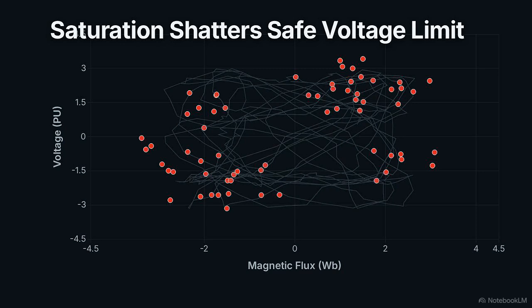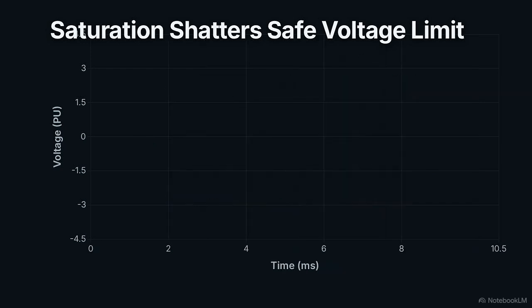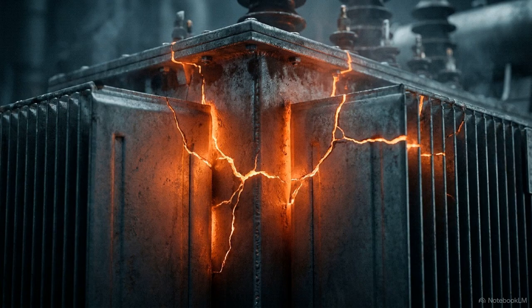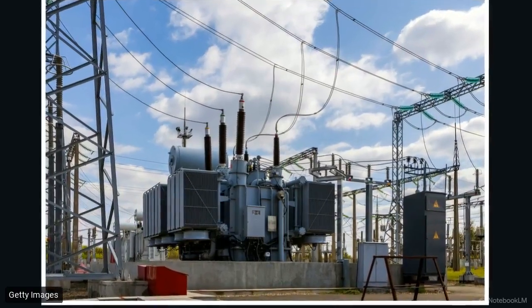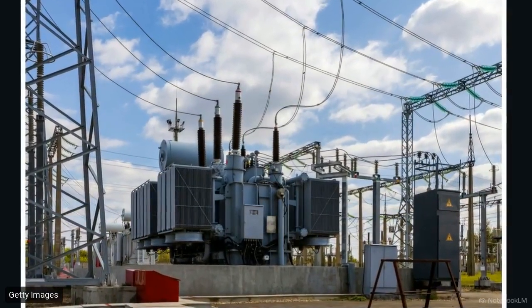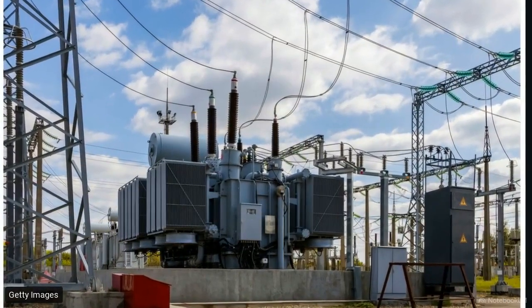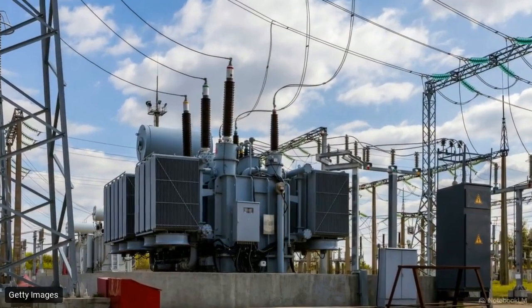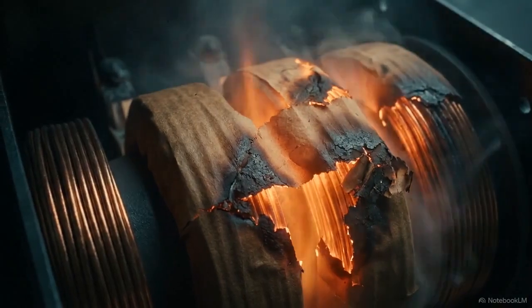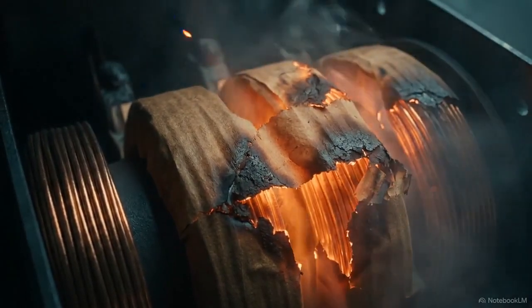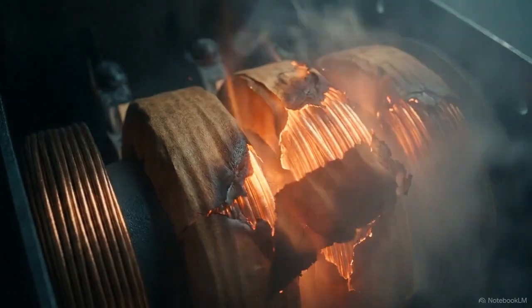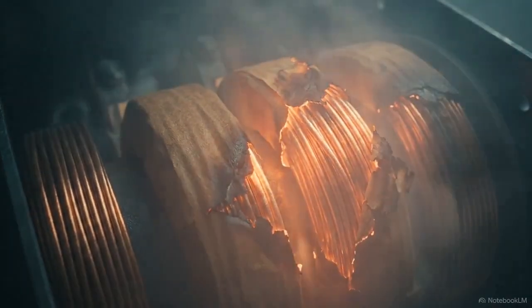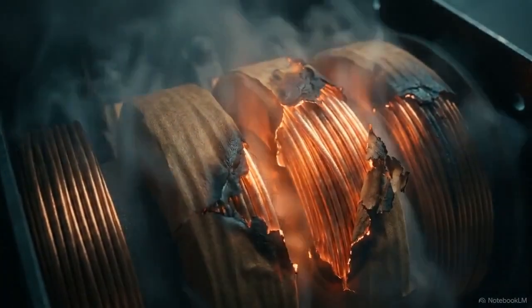Translating that math to real-world stakes, the voltage rockets to 3.88 per unit. That is nearly 4 times its normal, safe operational limit. This mathematical anomaly takes a heavy physical toll on the hardware. Inside the transformer, the magnetic core violently saturates, hitting its absolute magnetic limit, and then rapidly desaturates over and over again. This high-speed oscillation generates intense heat and extreme mechanical stress. The critical insulation protecting the inside of the transformer begins breaking down almost immediately.